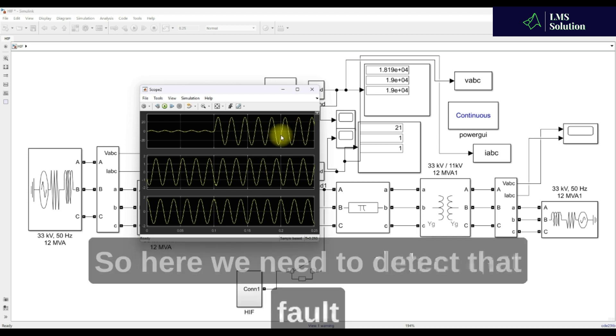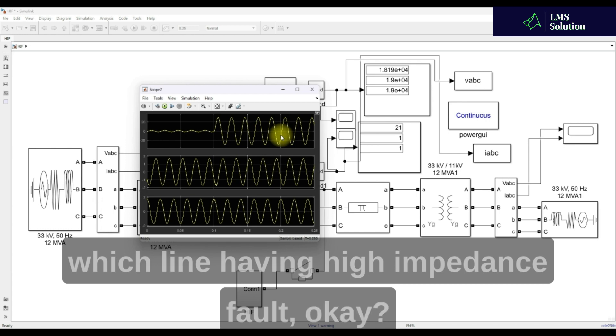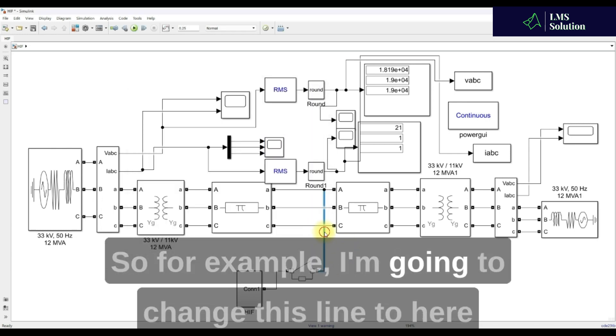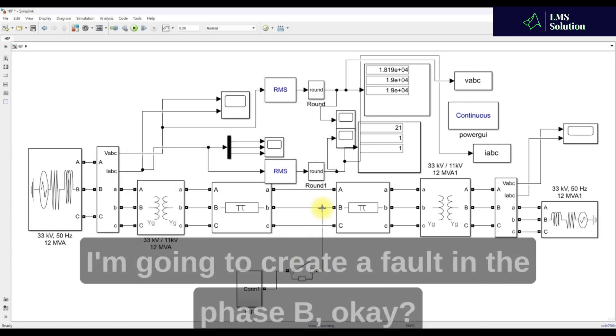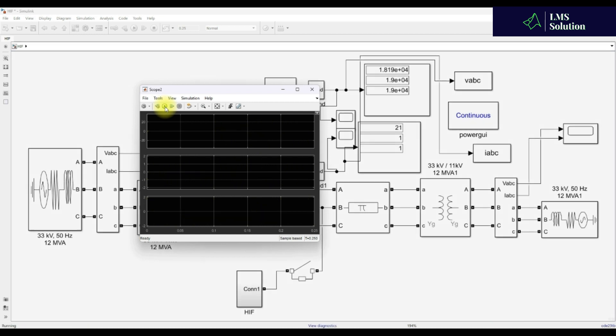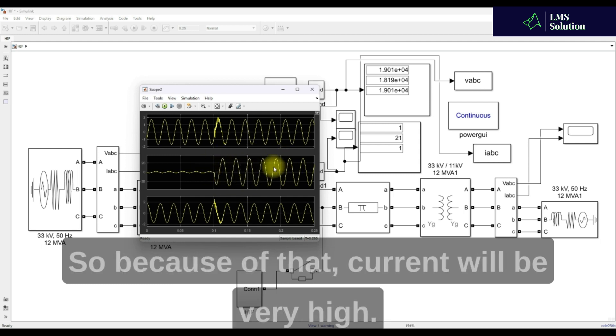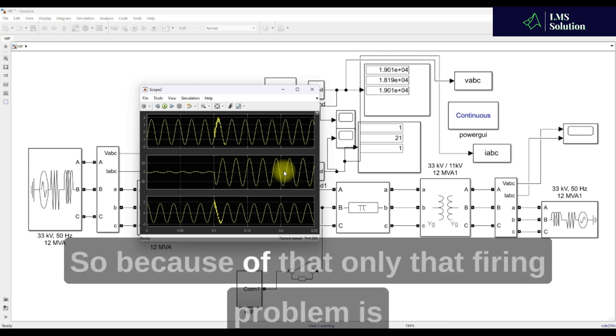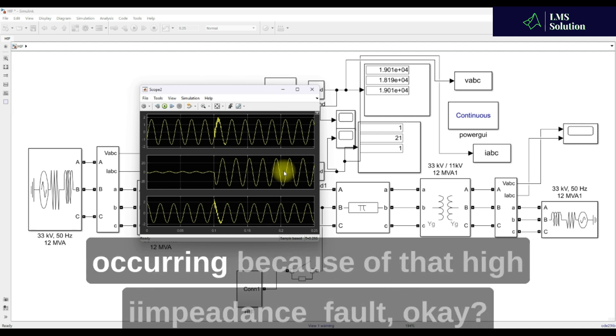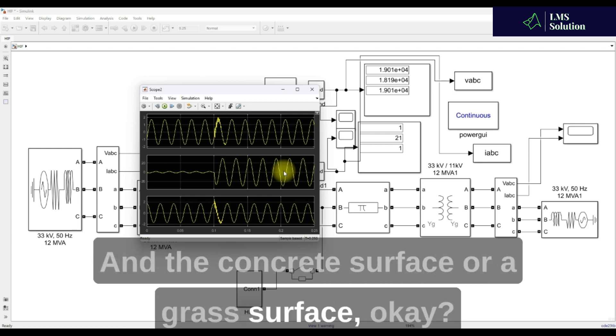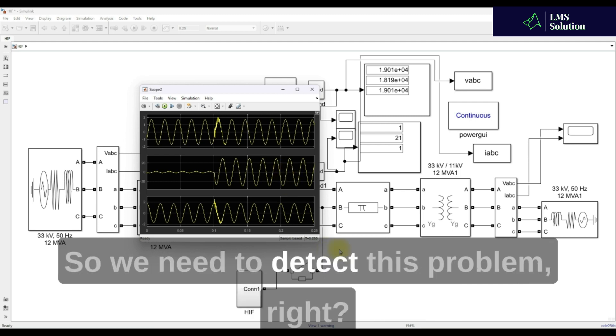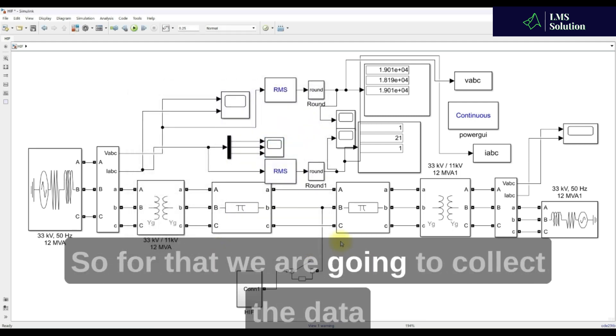We need to detect which line has a high impedance fault. Now I'm going to change the fault to Phase B and simulate the model. You can see that the problem is created in Line B only — the current becomes very high because of that high impedance fault on the concrete or grass surface.